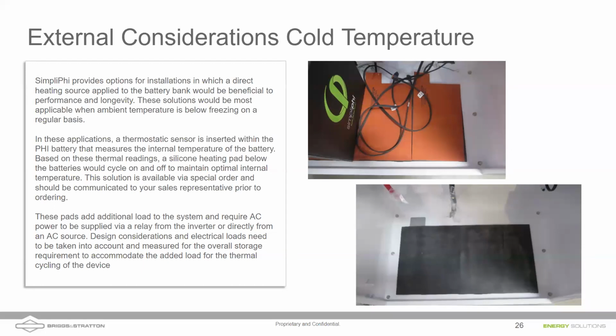So try to avoid this. And there are ways you can avoid it. One, you can use the battery cabinets. Two, you can use these wired-in heaters that are here. But charging quickly at low temperature once or twice, this takes hundreds of cycles to cause real damage. These batteries can last for 25 plus years if treated nicely. So it's not like a single cycle is going to ruin the battery, but you want to pay attention to not do this regularly. Daniel's giving you options for ways to do this.